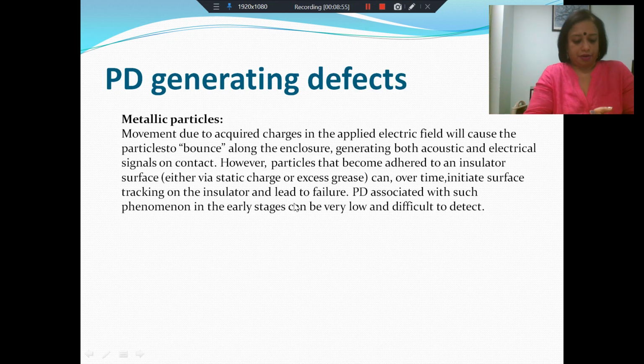So what are the reasons that cause PD inside gas insulated substations? We've already discussed this earlier, and it's quite obvious that the most important source of partial discharges is metallic particles. The metallic particles acquire charge, and when they acquire charge, they're accelerated by the applied electric field, and this will cause the particles to bounce on the enclosure. So they have this lift off, these hopping excursions, they bounce off and they fall again. When that happens, they generate PD, and the PD will generate both acoustic signals as well as electrical signals on the enclosure.